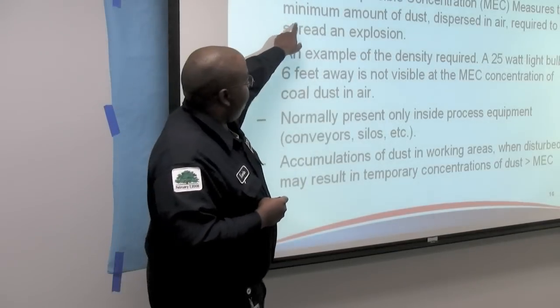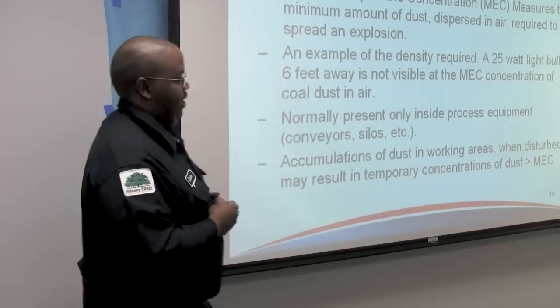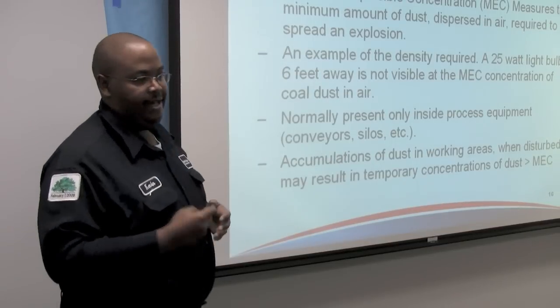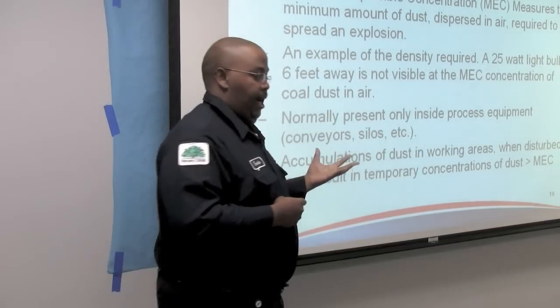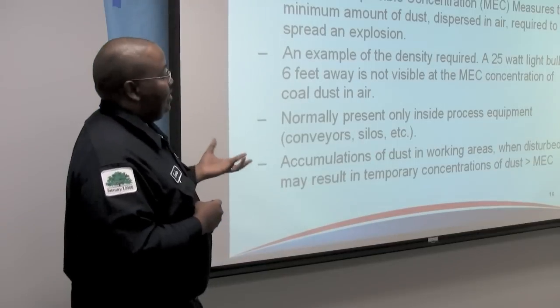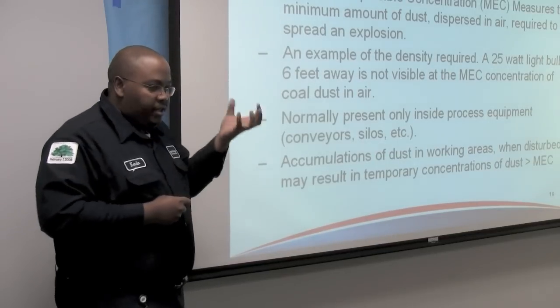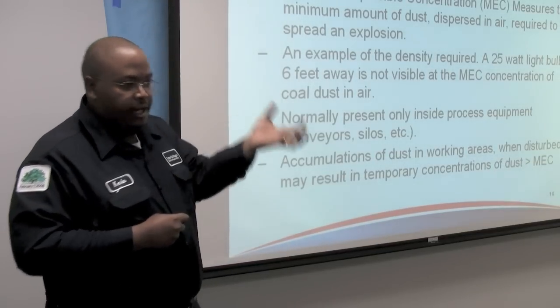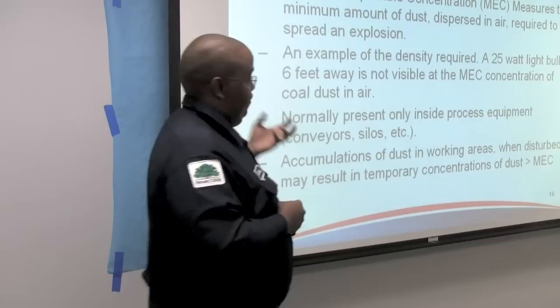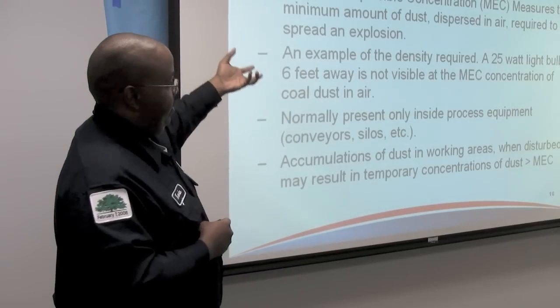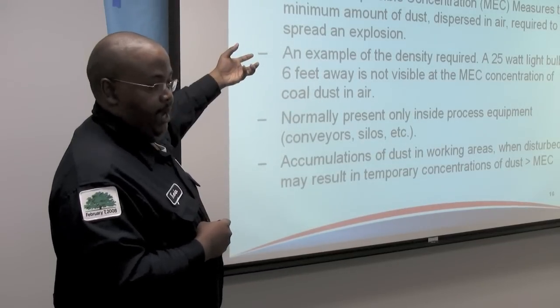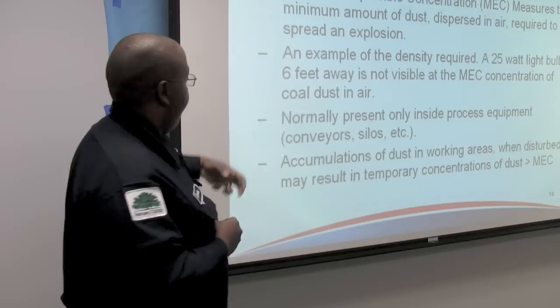The Minimum Explosible Concentration — MEC — you'll see that on material safety data sheets and in a lot of the literature you read. It's basically the smallest amount of dust that, when suspended in air and if it meets a source of ignition, will create a deflagration.